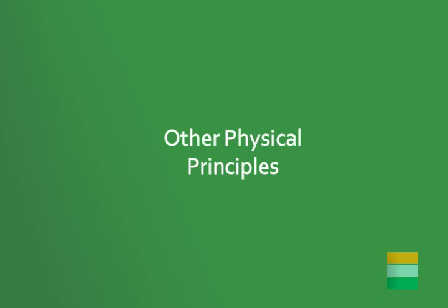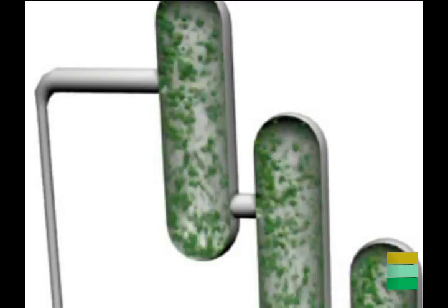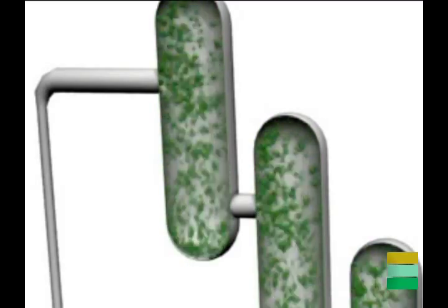The pressure differential between the injection from the refrigerant bottle and the suction of the compressor of the main machine creates a turbulent state, thus helping the removal of products from the interior of the circuit. The miscibility of acids with the oil in the internal circuit means that acids are extracted when the oil is removed. Furthermore, many solid particles created from the breakdown of the oil will be drawn out with it, and others are drawn out as a result of the pressure differentials.